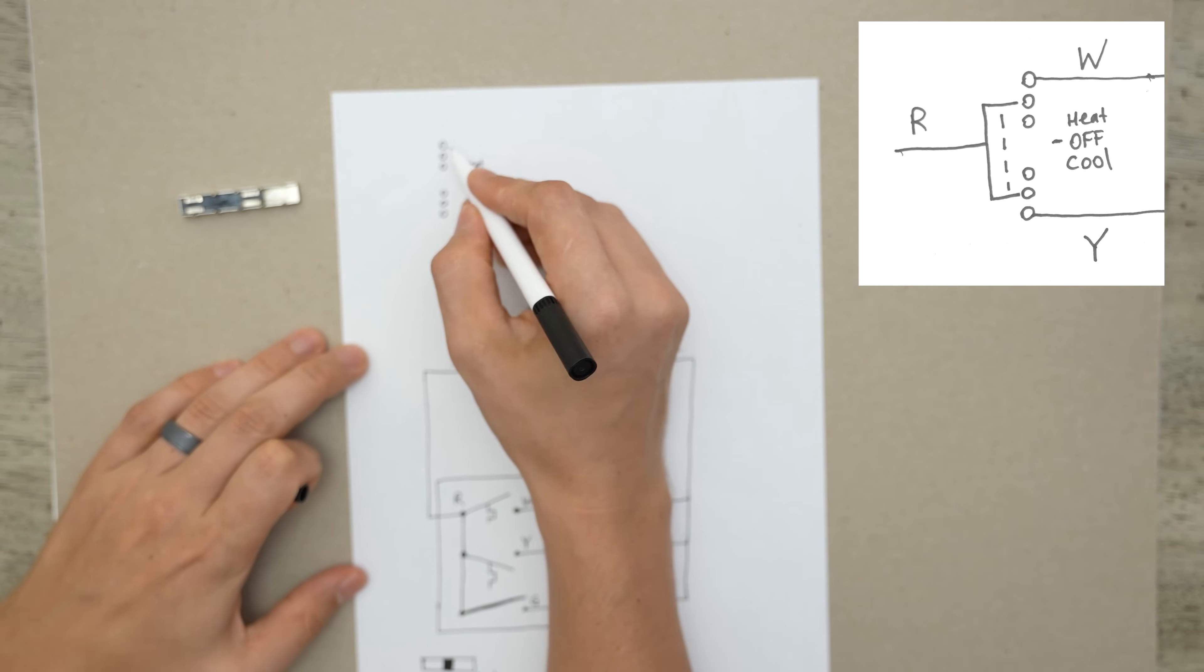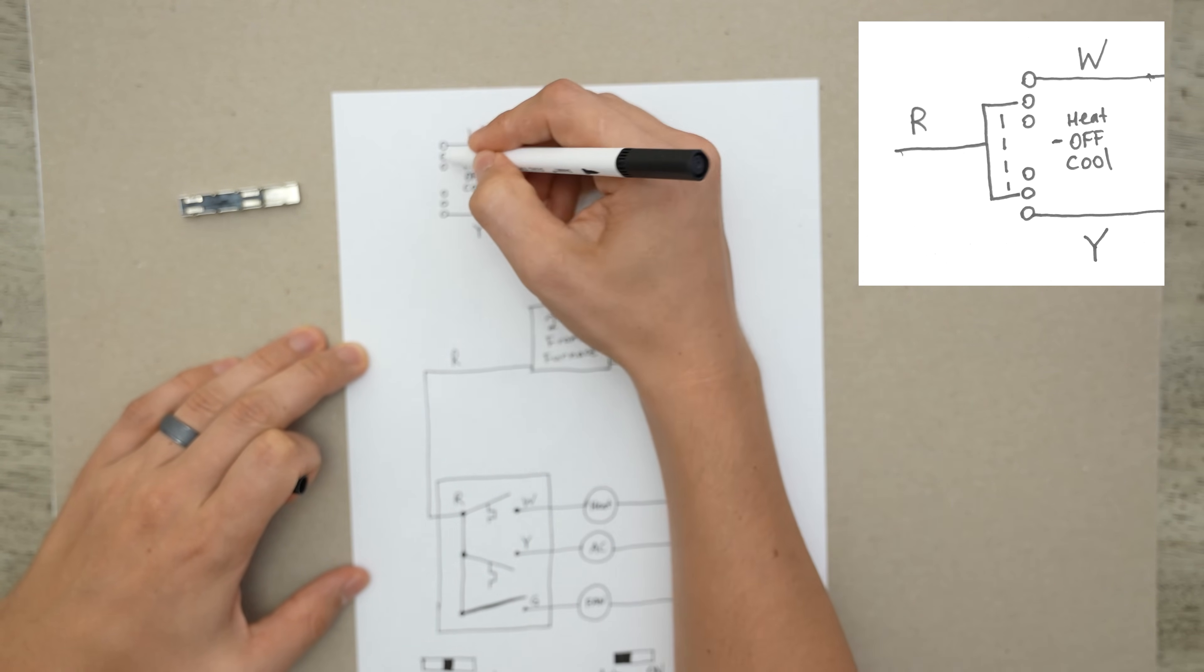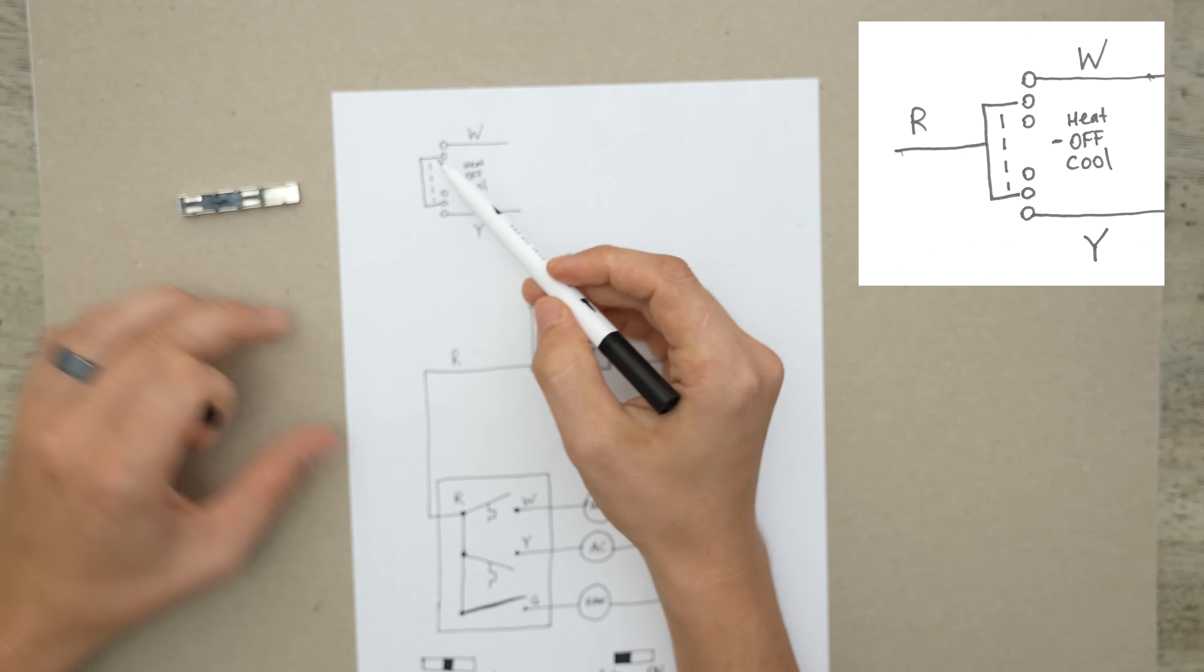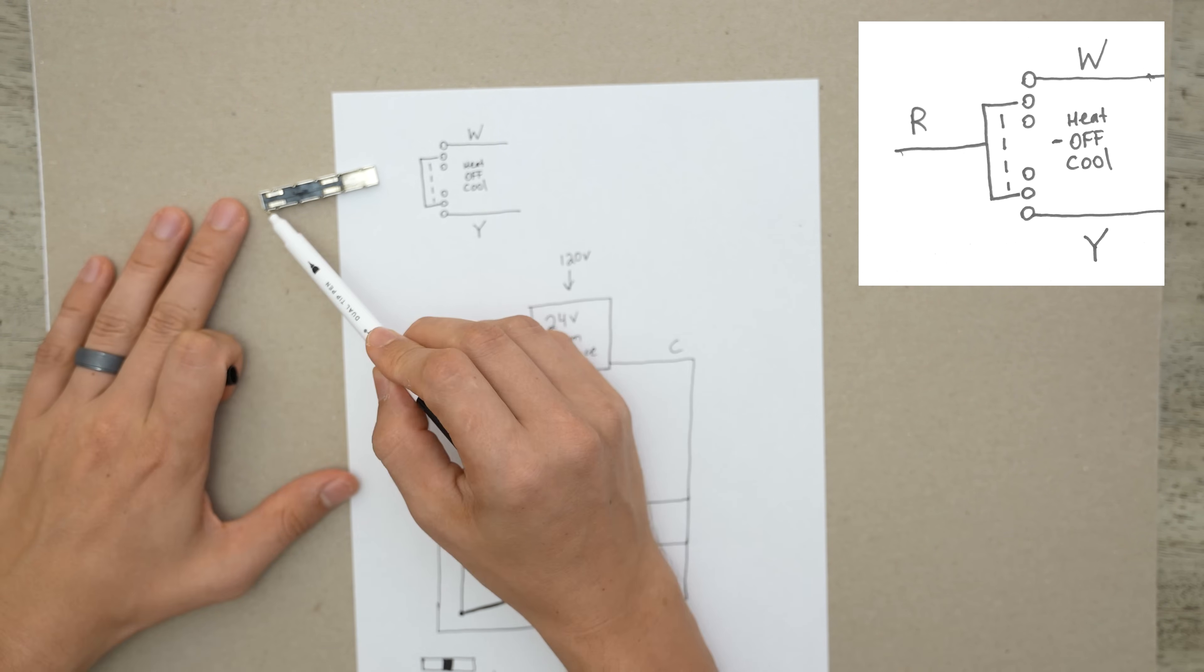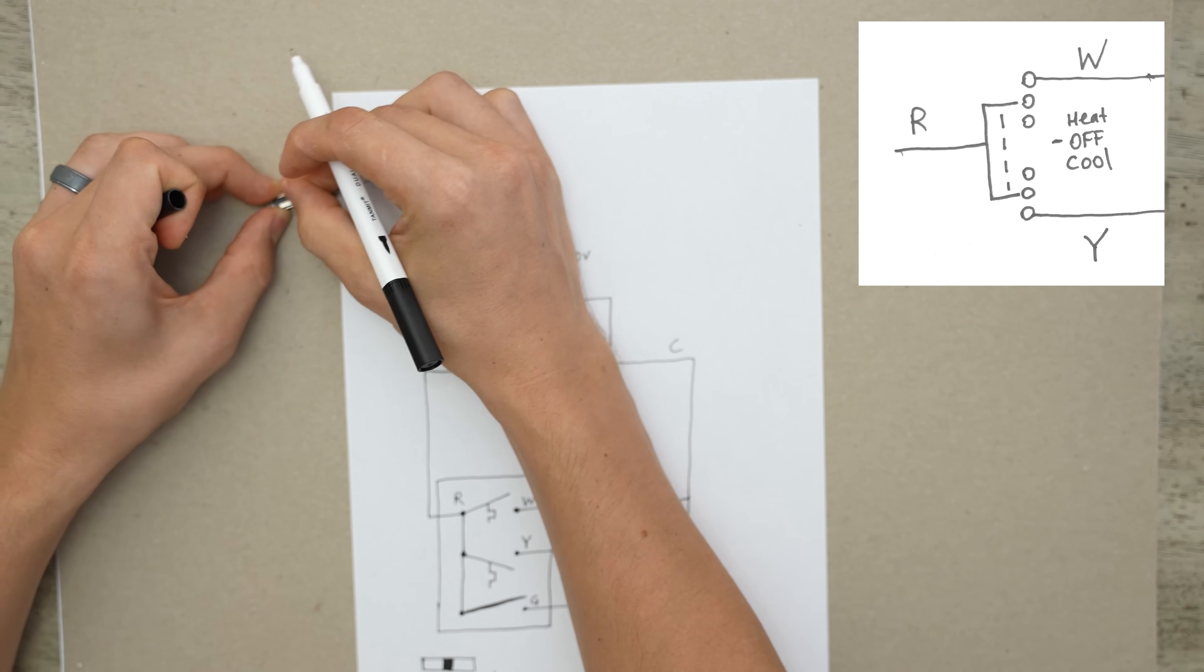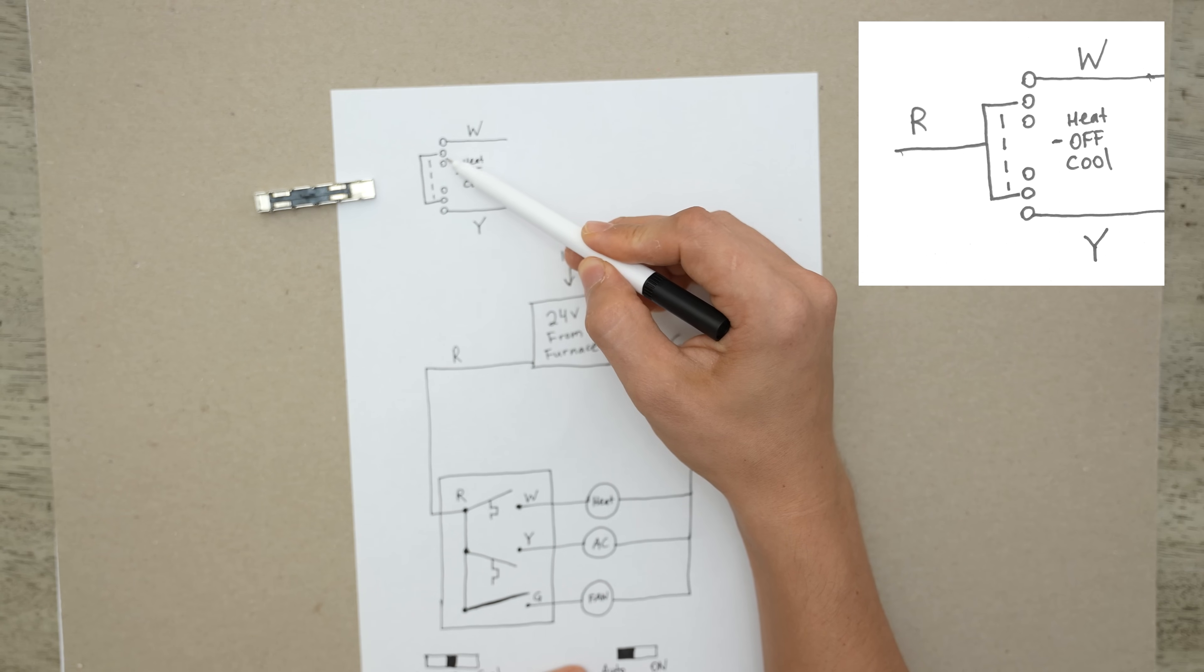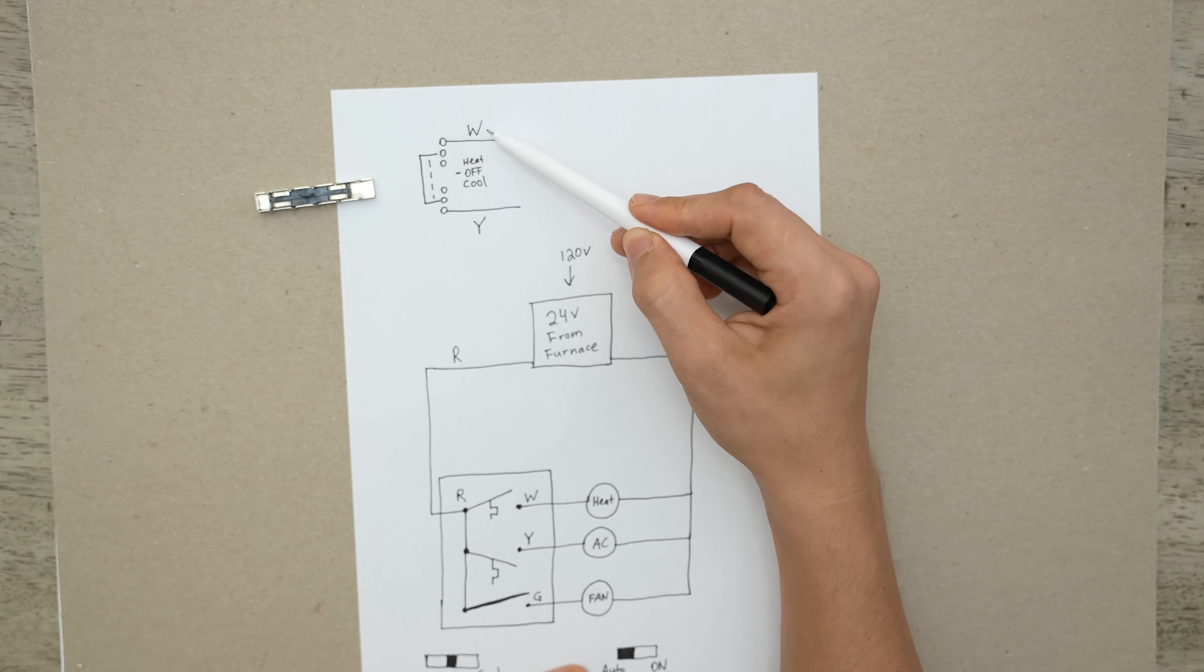Let's say this top one is going to be our W. The bottom one is going to be our Y. And let's draw our switch. This is the switch. So this is one side of the contacts, these guys right here. And this is the other side. Right now, it's in the off position, right here in the middle. If we take a look at these contacts, these two over here are blanks. There's nothing hooked up to them. But the one on the top and the one on the bottom, they are hooked up to the AC and to the heating.